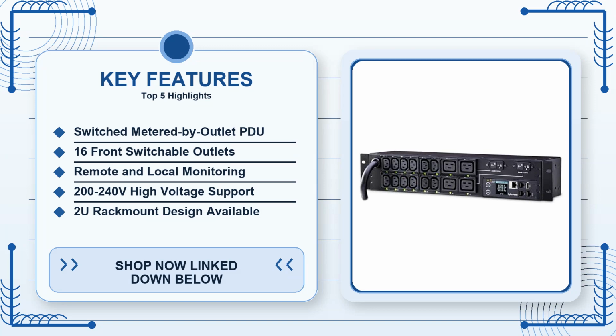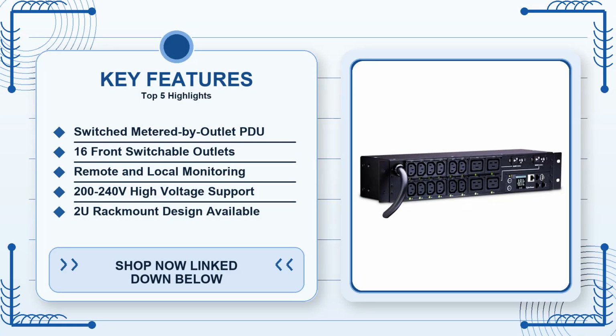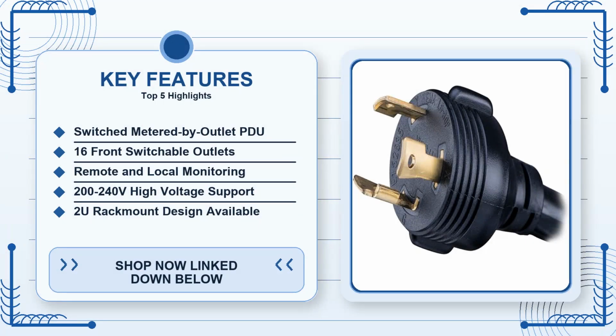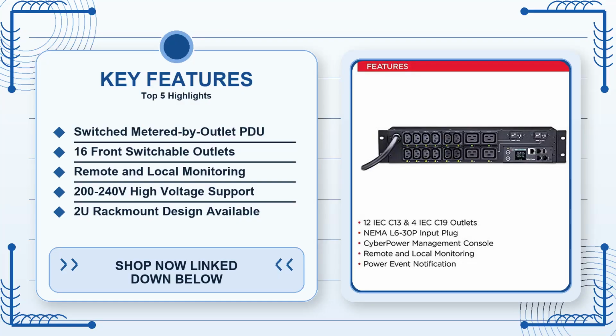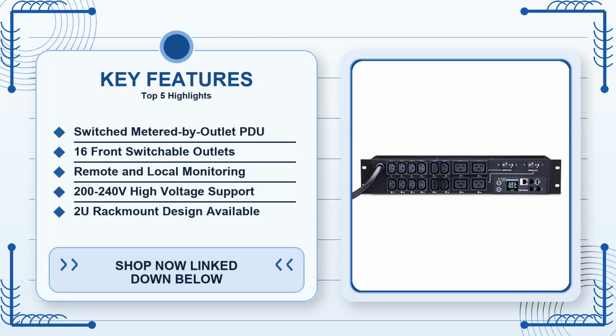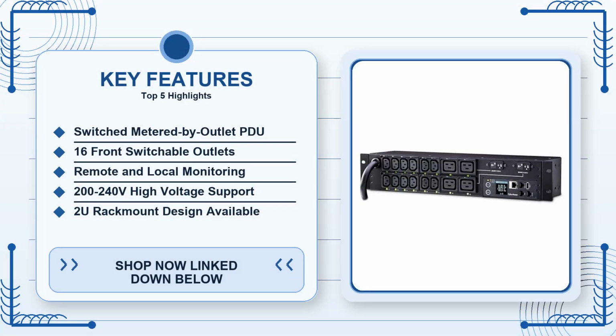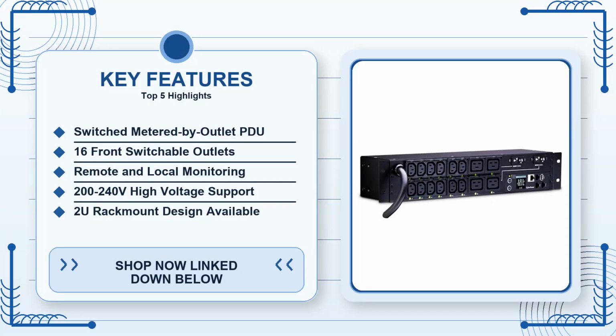The real power comes from the metered-by-outlet monitoring. Using CyberPower's PowerPanel software, you get a live feed that shows you amps, volts, and watts per outlet. In a real-world scenario, imagine you're running a test lab for a new web app, and you notice your server's power draw spikes to 12A during a stress test. With this PDU, you can instantly see which outlet is the culprit, confirm whether the spike is within acceptable limits, and decide if you need to spread the load across another PDU or upgrade your cooling. That immediate feedback can prevent hardware from overheating before a fire alarm even thinks to go off.